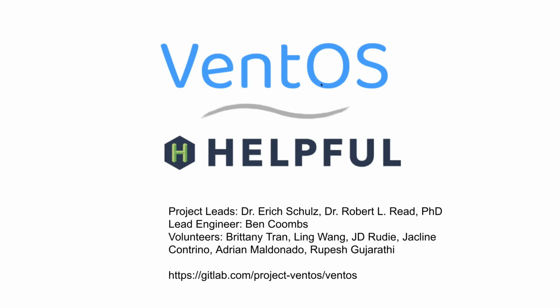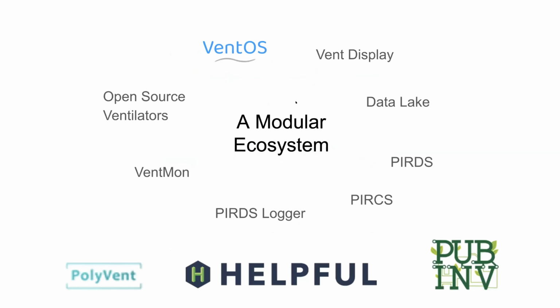VentOS is designed to be part of a modular ecosystem of components, which allows teams to pick and choose what works for them and replace and upgrade ones that don't. The long-term goal of VentOS is to develop an FDA-approvable open-source ventilator firmware that could be used in various ventilator hardware platforms. One difference in this project is that we're not making a ventilator, but rather just the complex software and control systems, along with all the testing and documentation that's required to go with that.